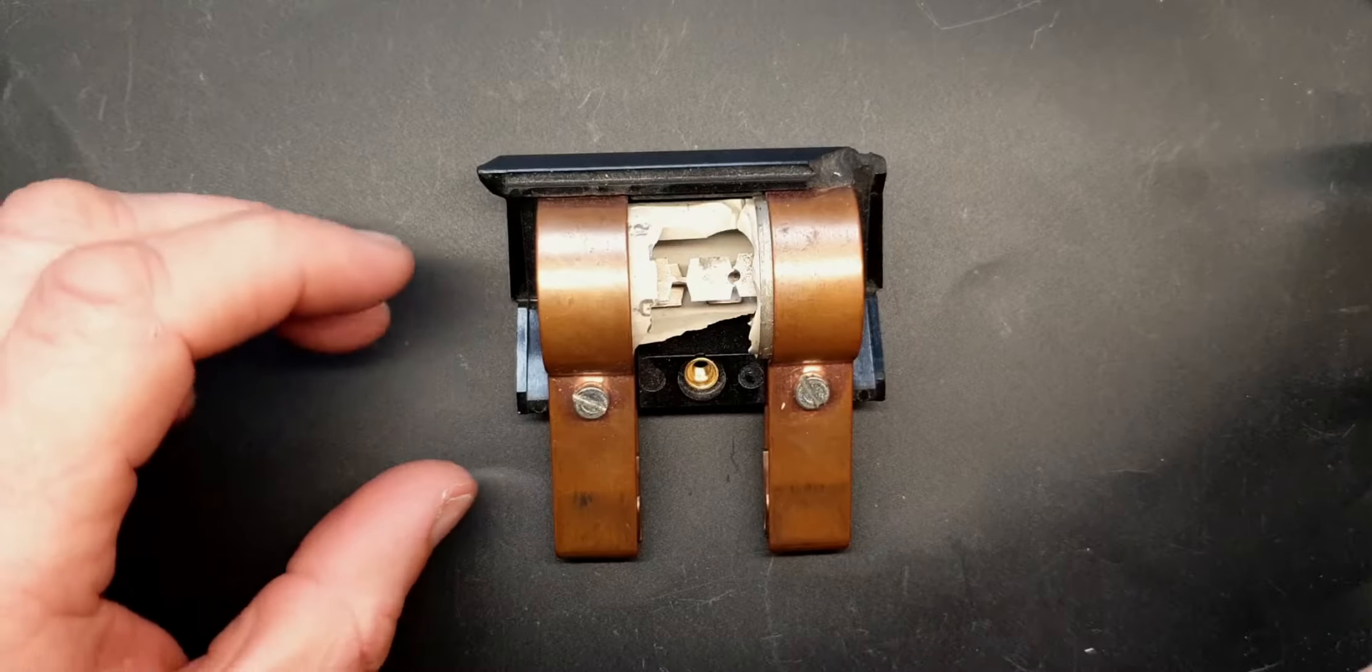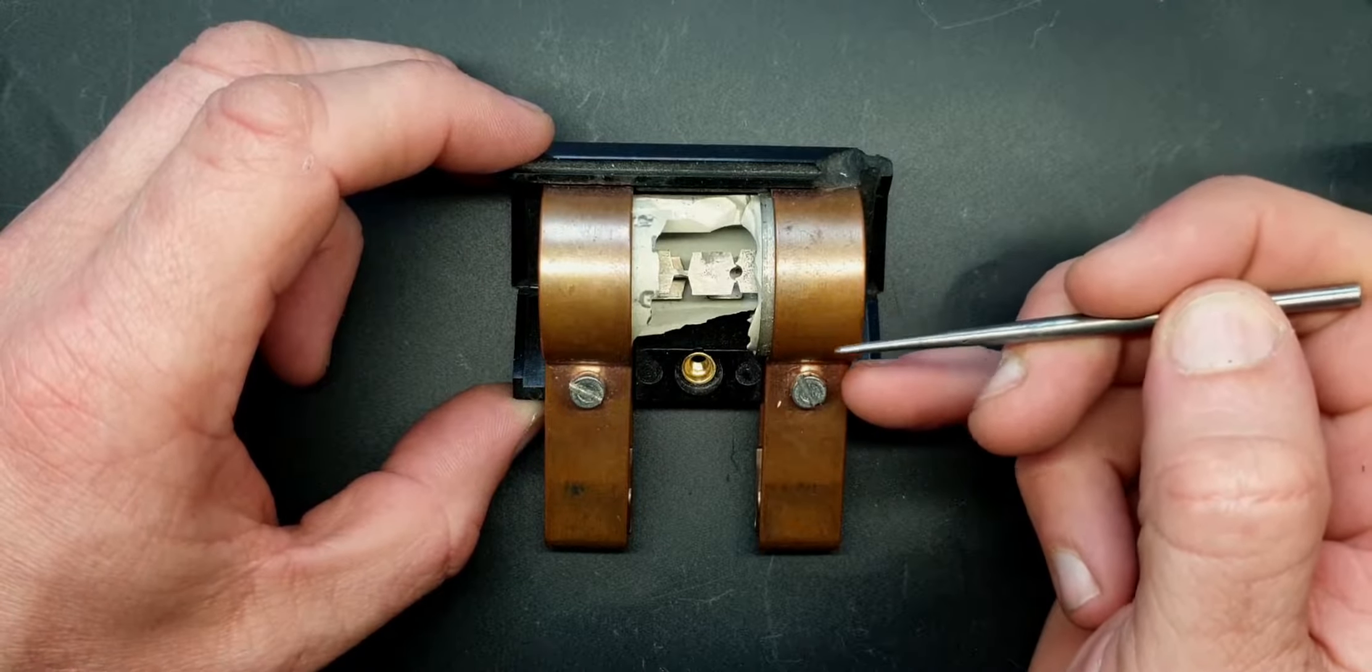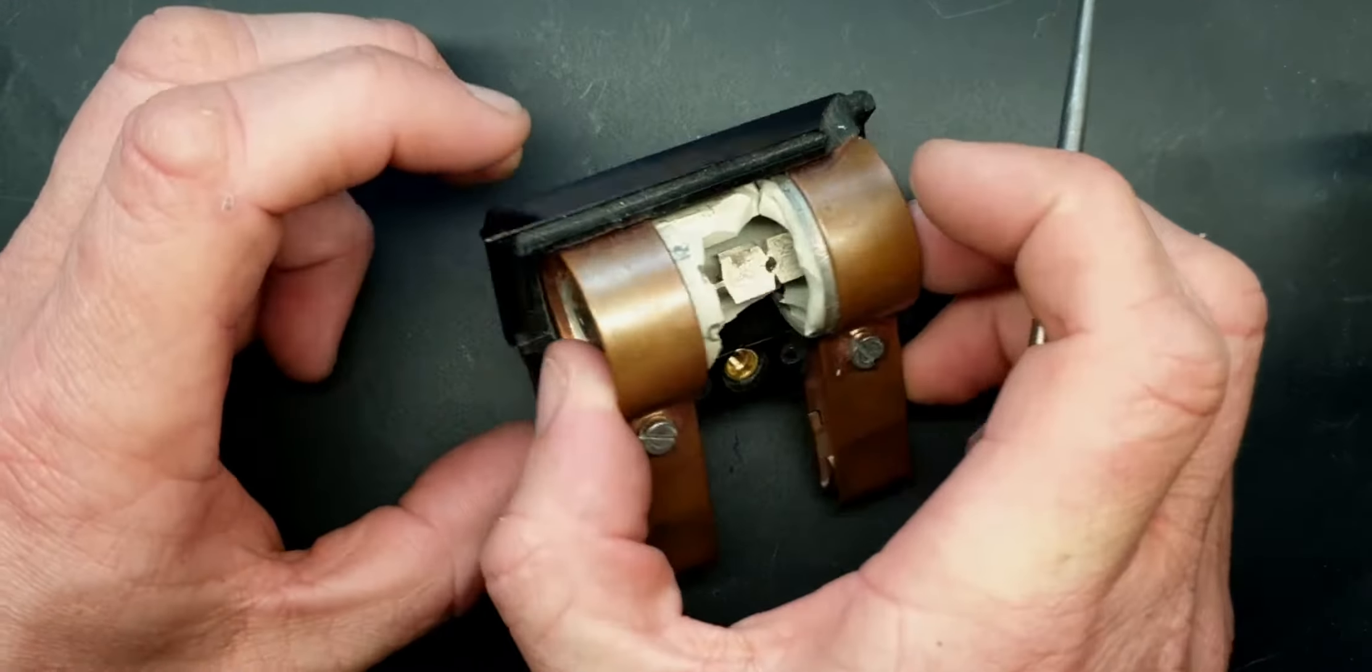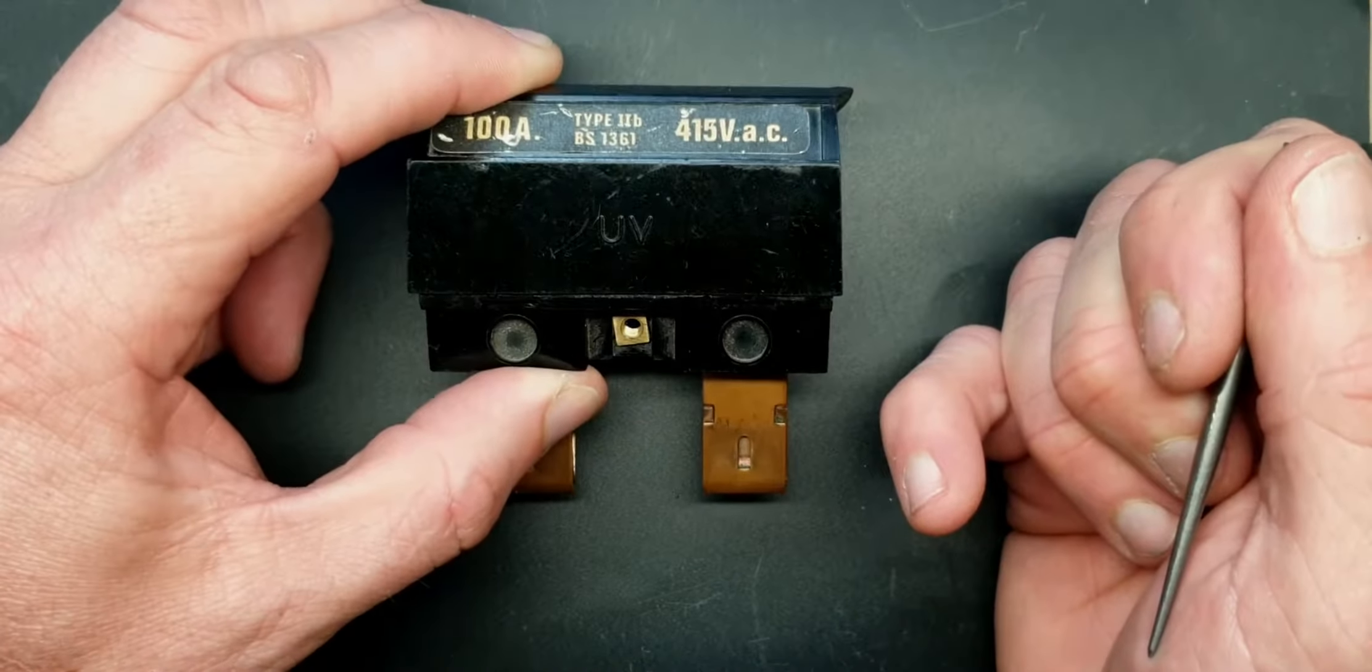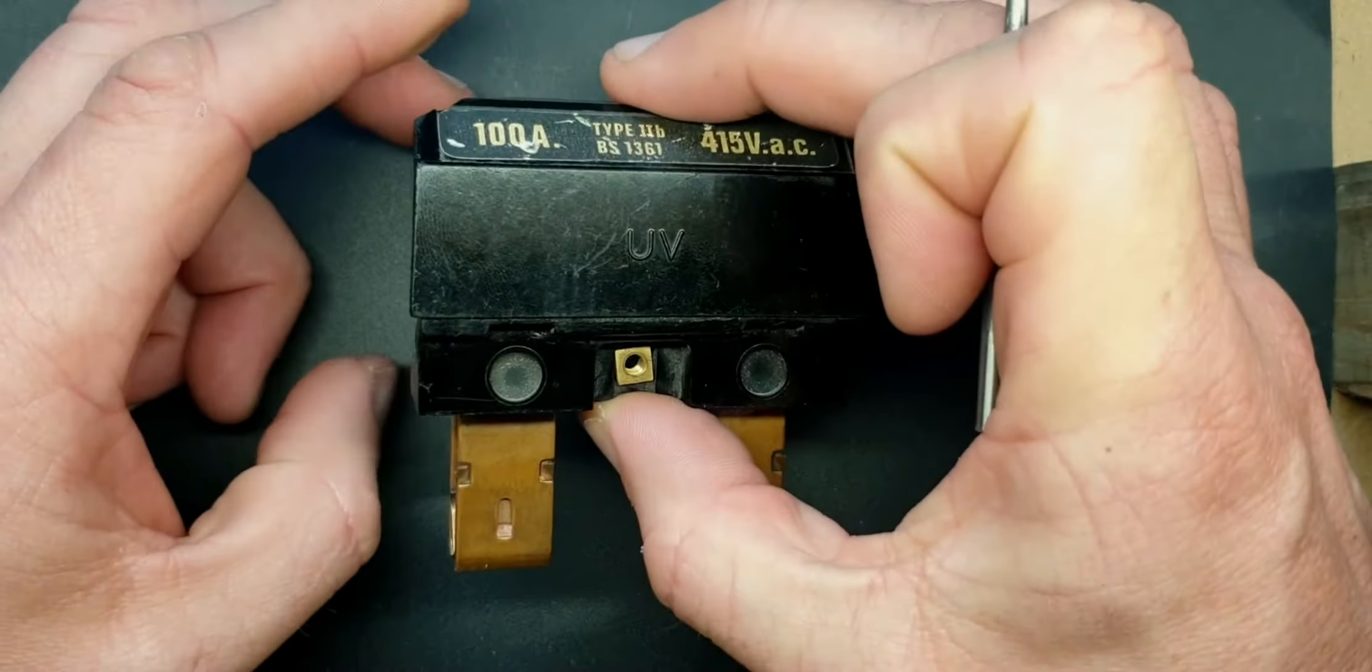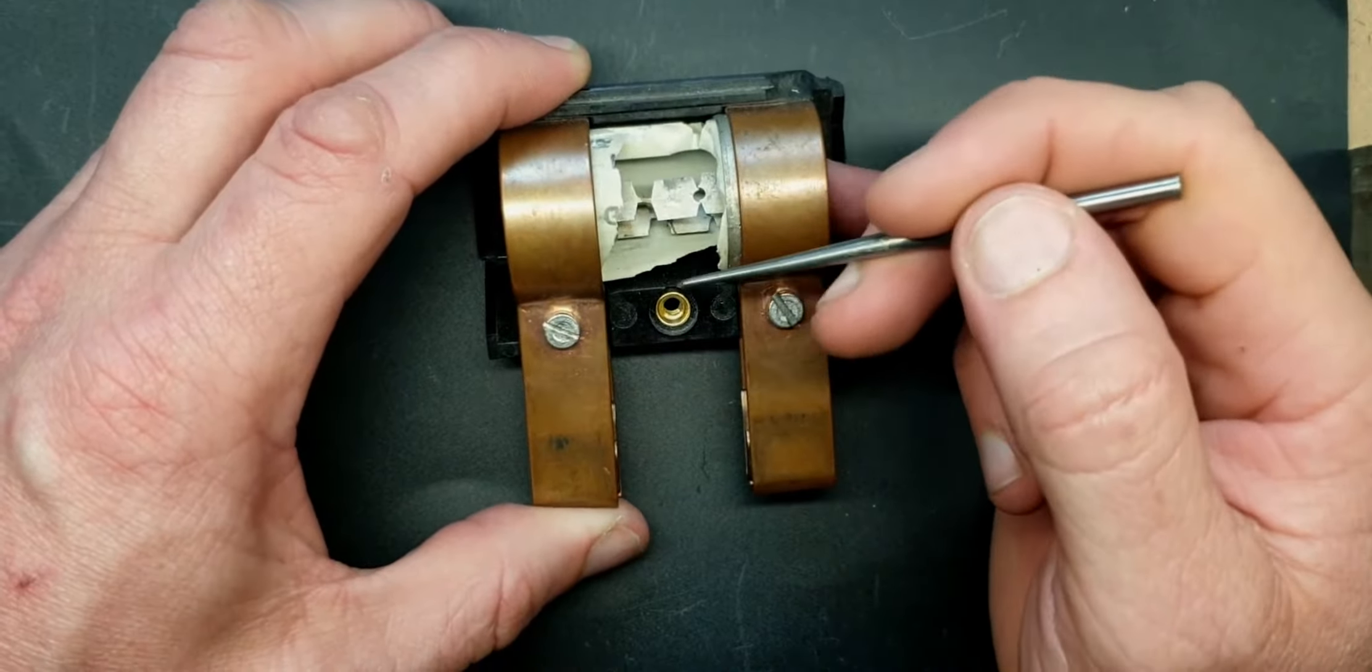Okay guys, what we've got here is an HRC or high rupturing capacity, or HBC high breaking capacity fuse. This one here is a BS88 in a standard domestic 100 amp fuse holder, similar to what you get on the incoming supply of a domestic premises. This is an 80 amp fuse, so the holder can take 100 amps, this fuse itself is only an 80 amp fuse.